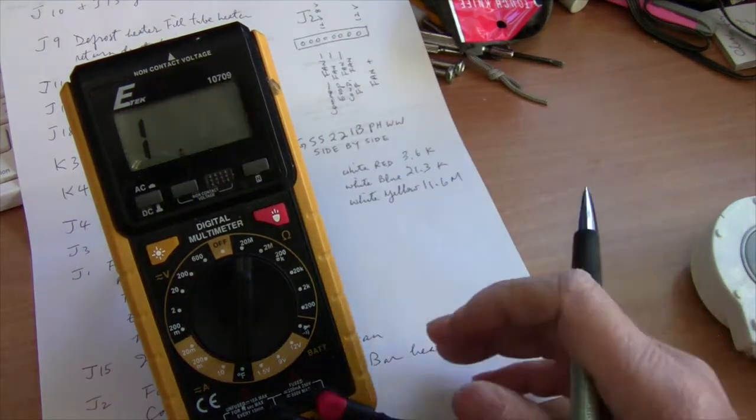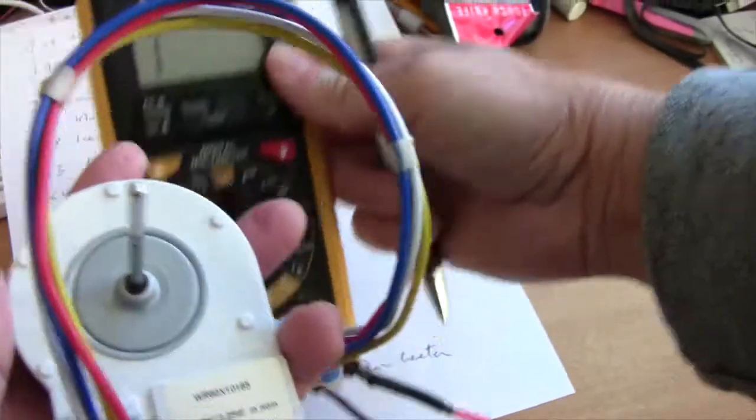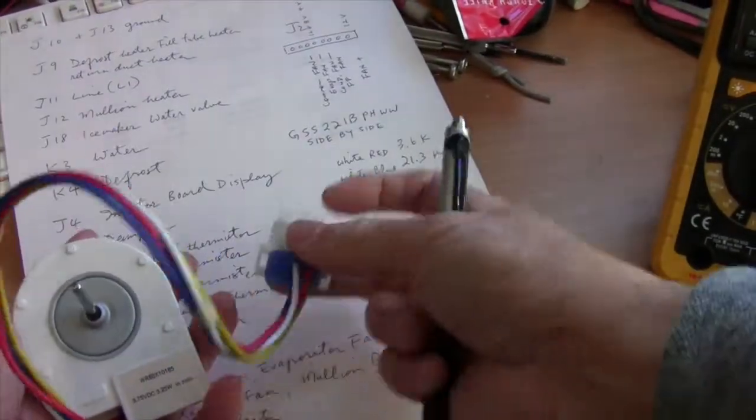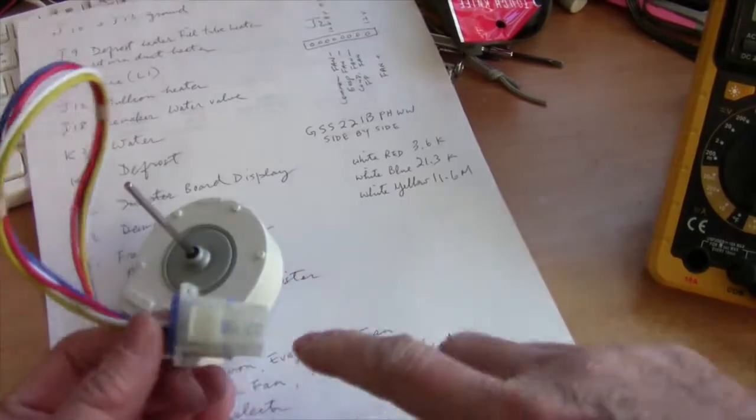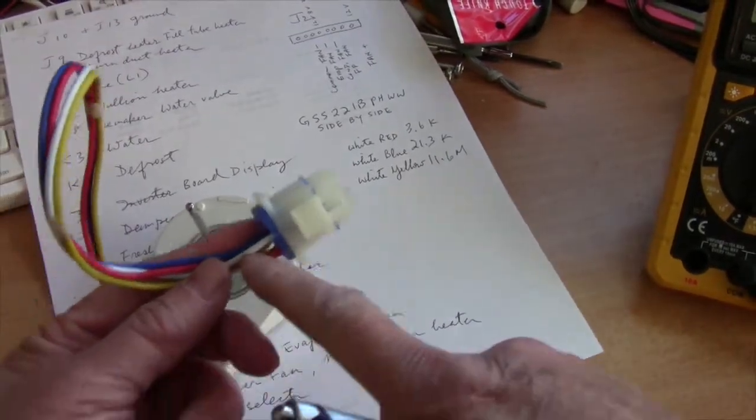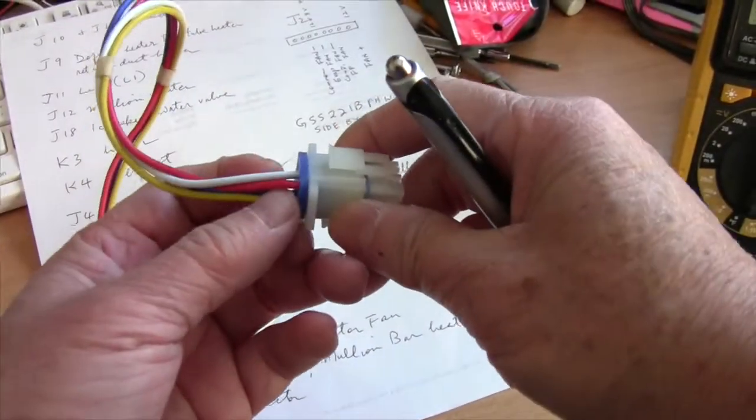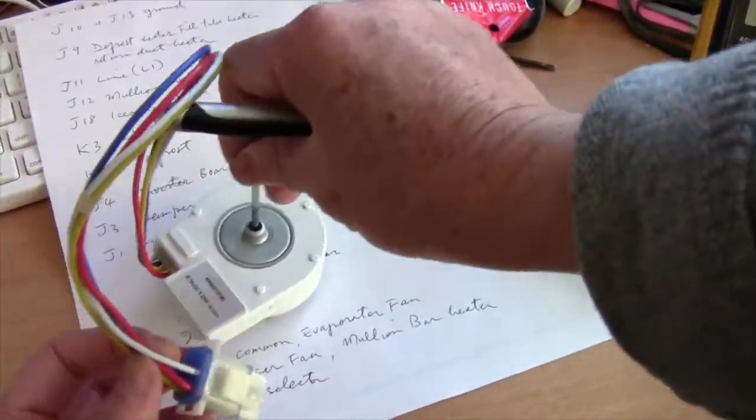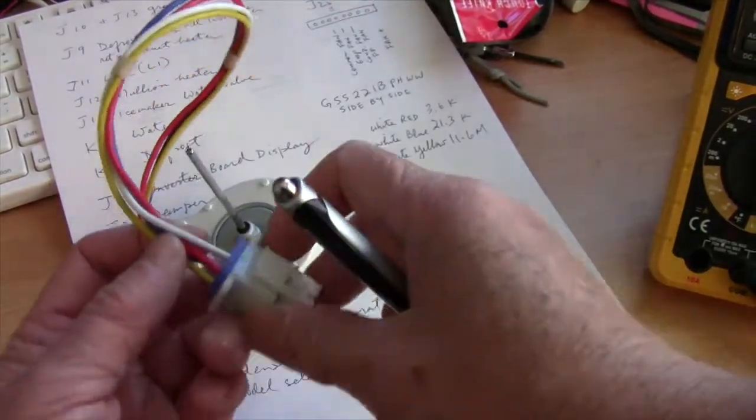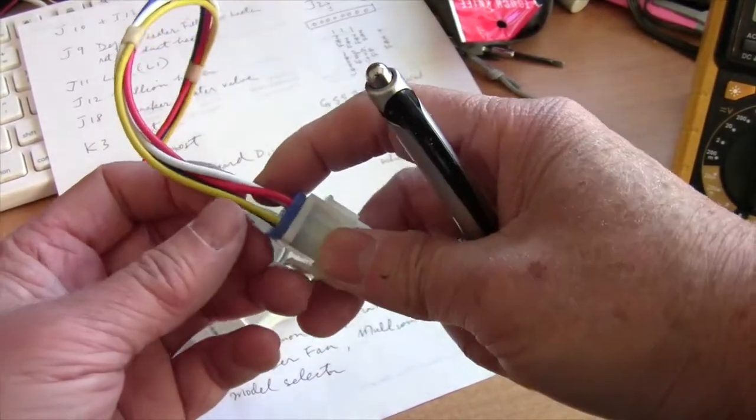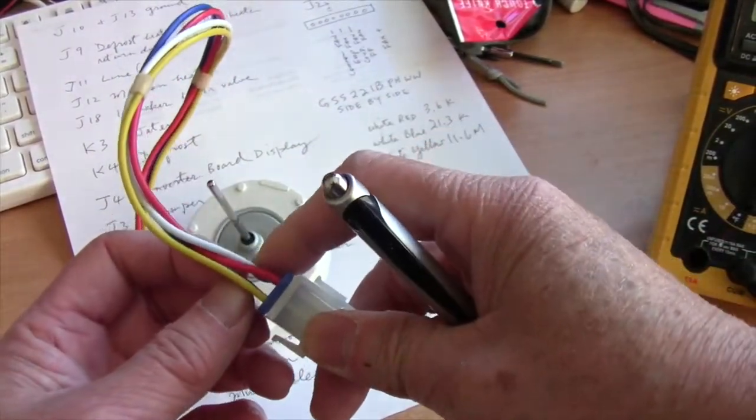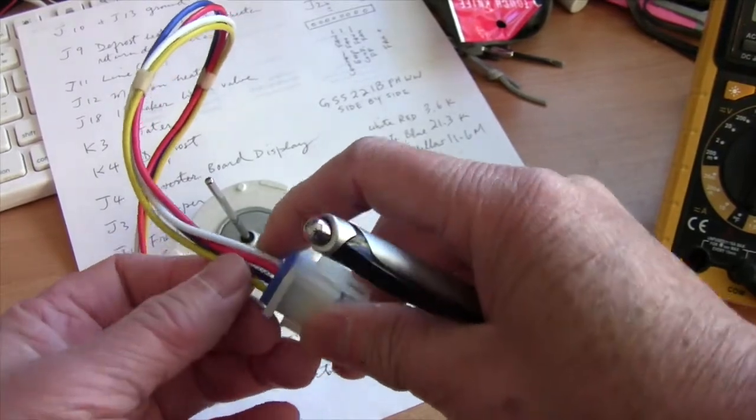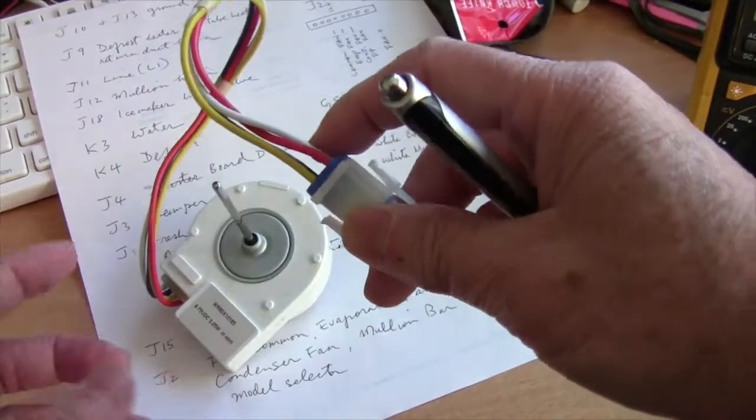So those will be the values for your fan motor. You can also, of course, apply a 12 volt DC voltage to this. This is the ground and the red would be the positive power wire, 12 volt. You'll see the motor turn, or the white and the blue would be a lower speed. And then the white and the yellow would be the lowest speed.